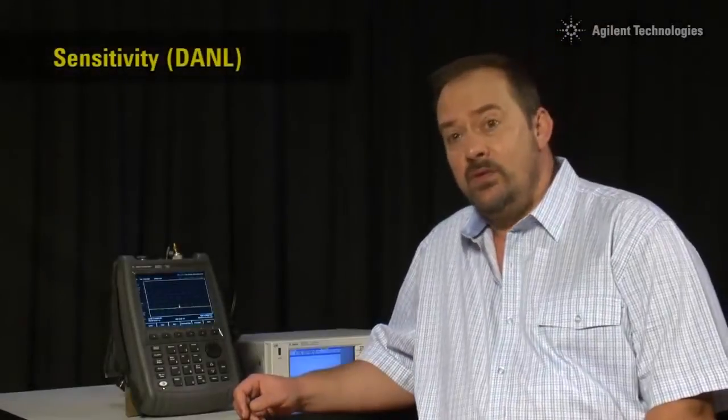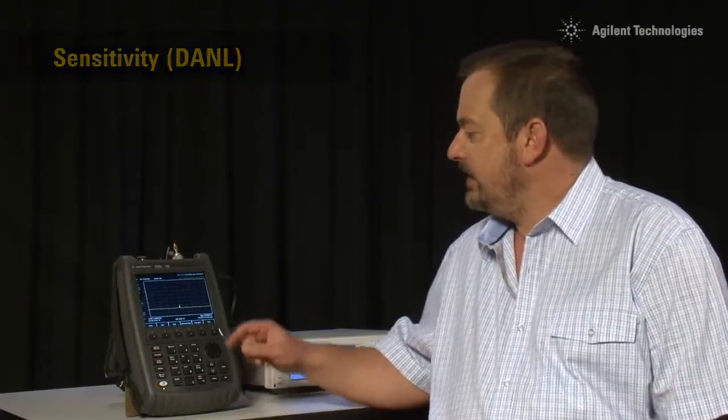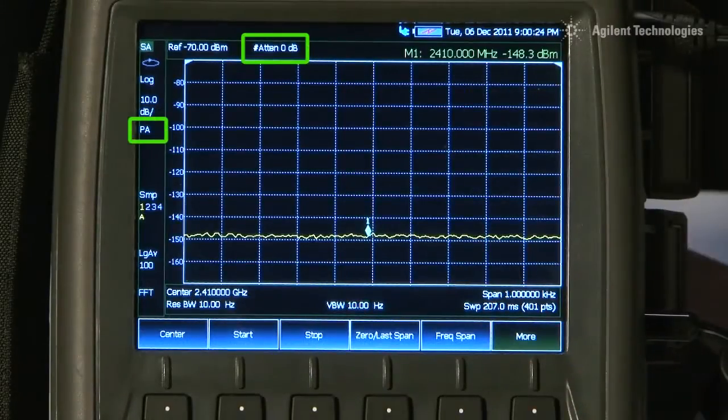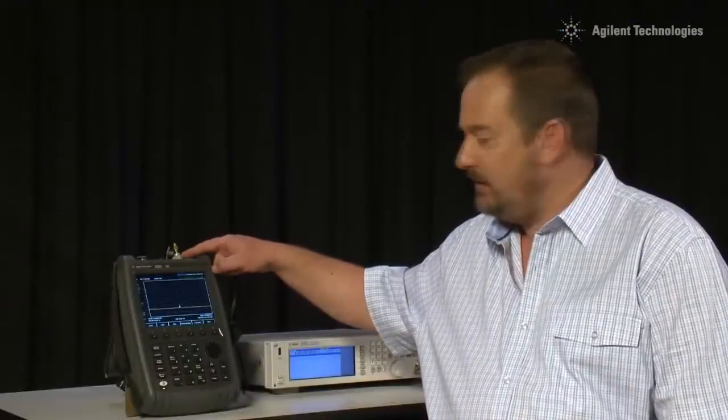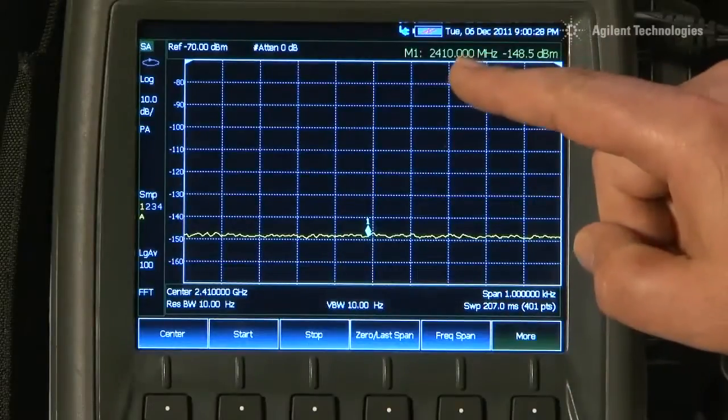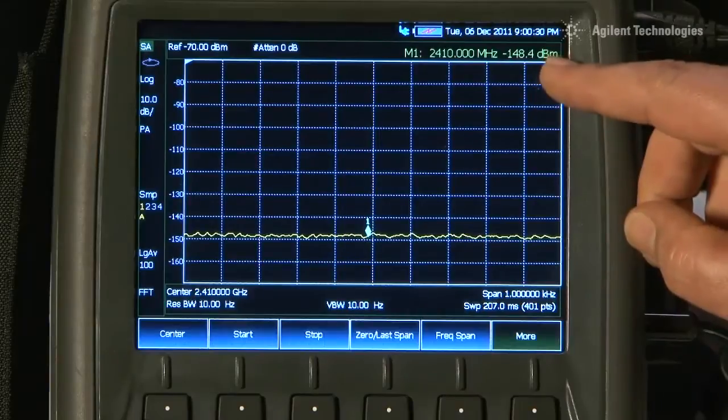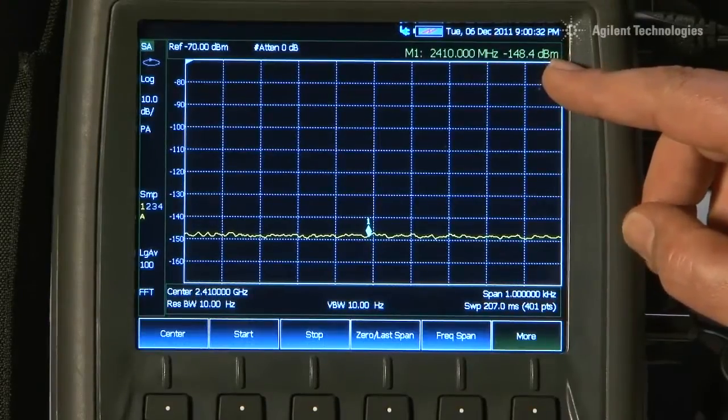A key specification of all spectrum analyzers is their sensitivity, or ability to detect weak signals. Here you can see with the attenuation set to zero, the pre-amplifier turned on and the input terminated with a 50 ohm load, that at about 2.4 GHz, it is achieving a noise floor of around minus 148 dBm.